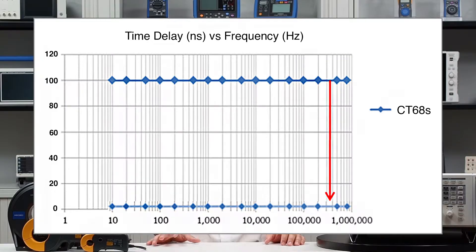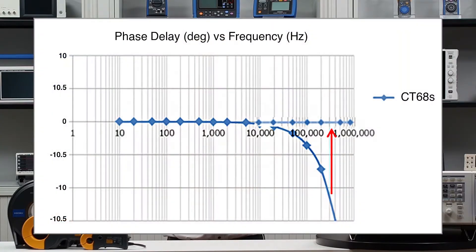Here is how this delay looks for a Hioki CT68 series current sensor. The time delay is shown in nanoseconds against the frequency. Of course, 100 nanoseconds of delay at 100 Hz doesn't have the same impact as 100 nanoseconds at 1 megahertz. This becomes clear when translating the time delay into phase delay values described in degrees. To make things as straightforward as in this case, you need a current sensor where the time delay is the same regardless of the frequency. With Hioki current sensors like the CT68 series, this is the case. So coming back to the deskew function, you only need one value to compensate the phase shift of the sensor — this is one of the things that makes Hioki sensors special, but it's not standard for current sensors currently on the market.